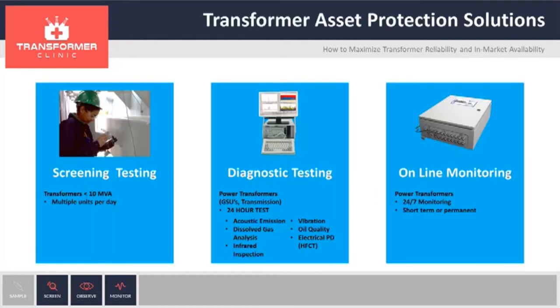Basically, we have three different solutions depending on the size of the transformer. The first one is for transformers smaller than 10 MVA — we can do multiple tests per day. The next step will be a diagnostic test, which is typically a 24-hour test, because we want to have all the load changes, temperature changes, and operating changes during that period. This is applied for power transformers that have several hundred MVAs, such as a transmission transformer or generator step-up transformer. And if you have a critical unit or an active fault, we can do continuous monitoring.